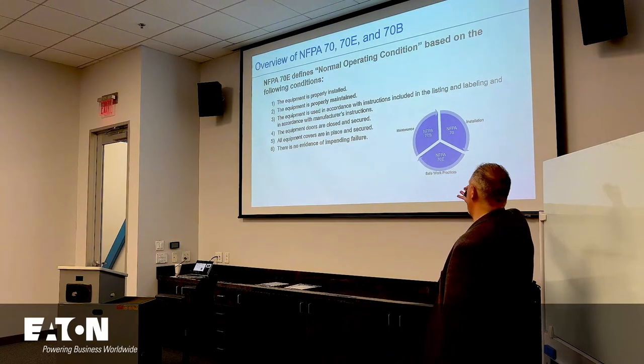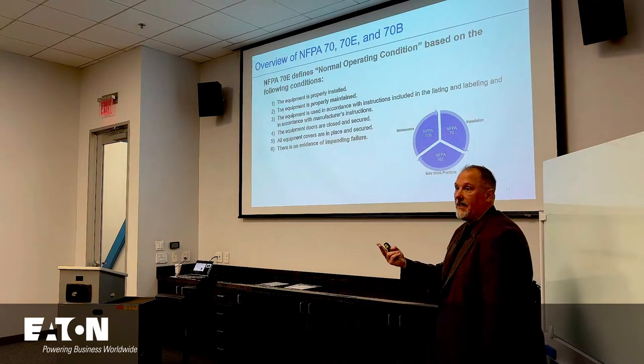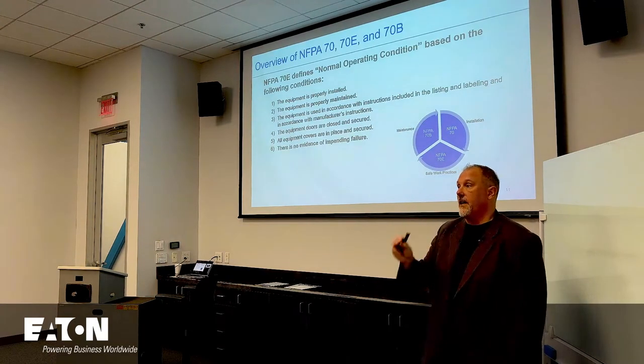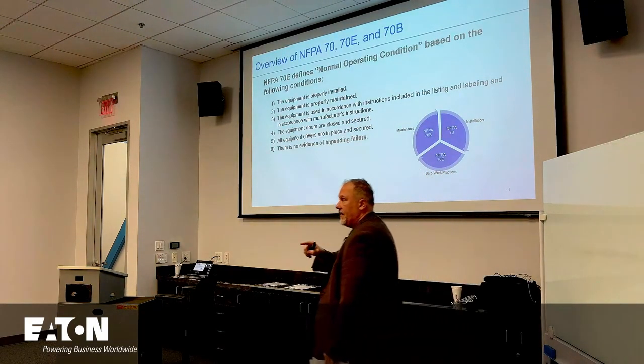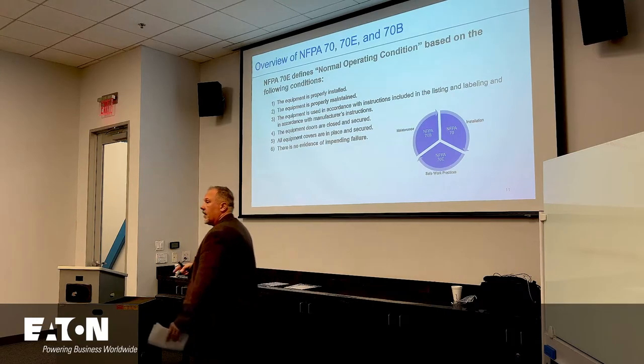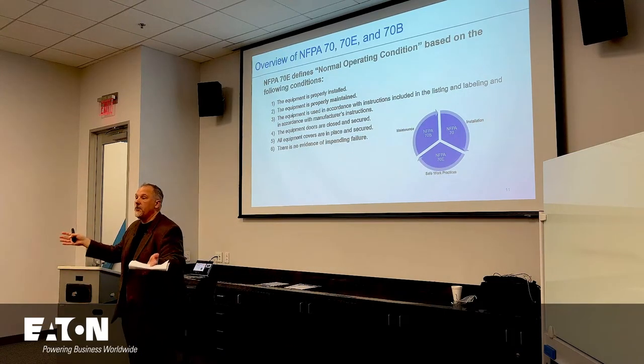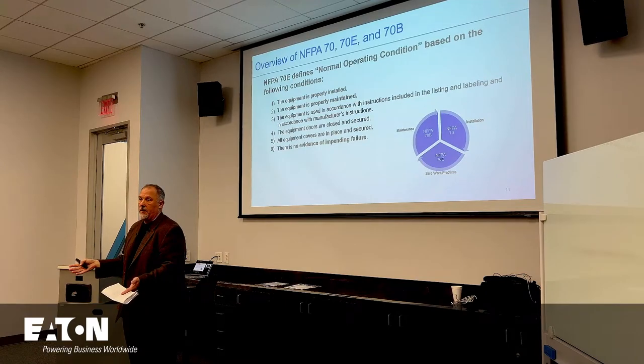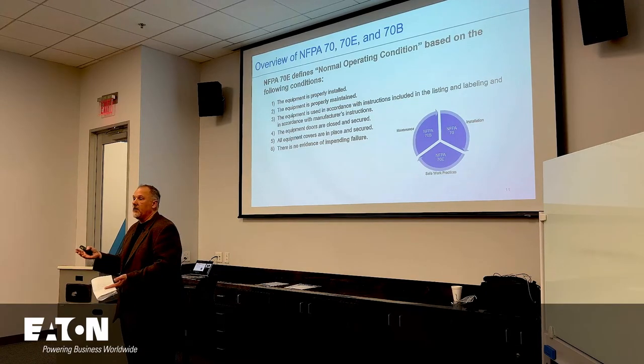I call that the trilogy, right? 70, 70E, 70B, they all work together. If I didn't install it correctly, 70E will tell you that you have equipment that's overduty from a fault current perspective. The interrupting ratings on your circuit breakers are exceeded.